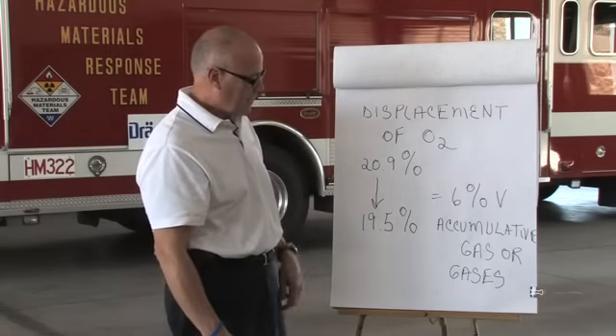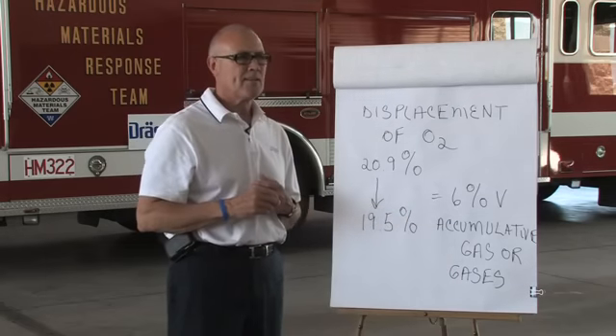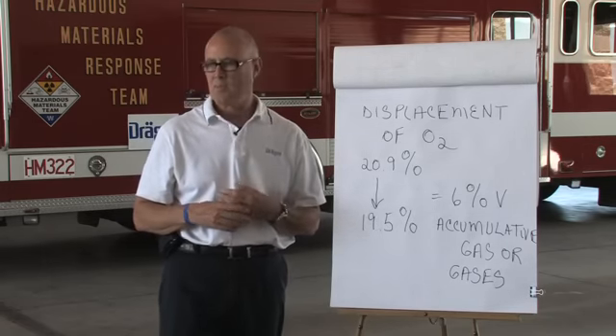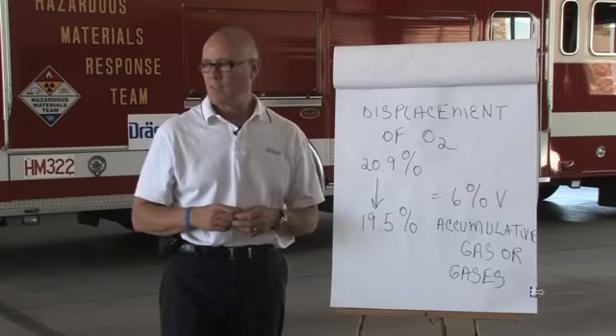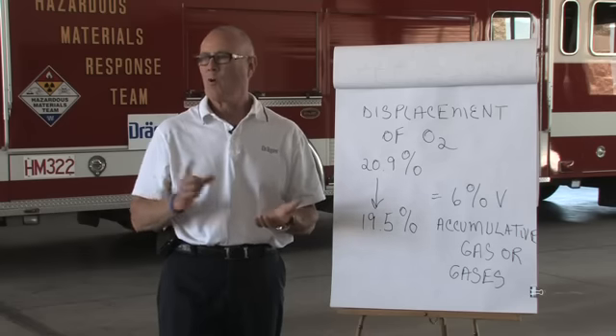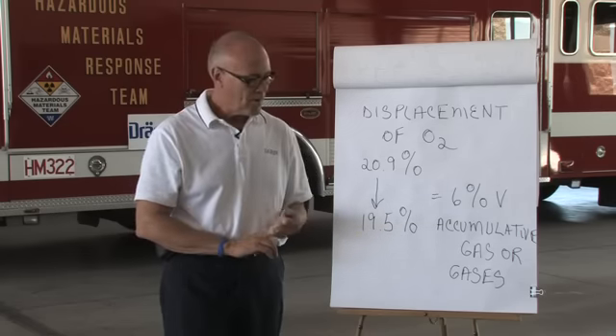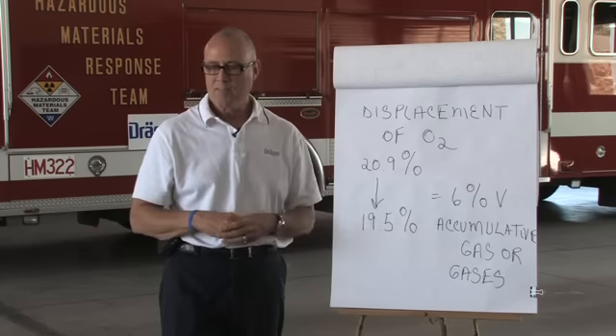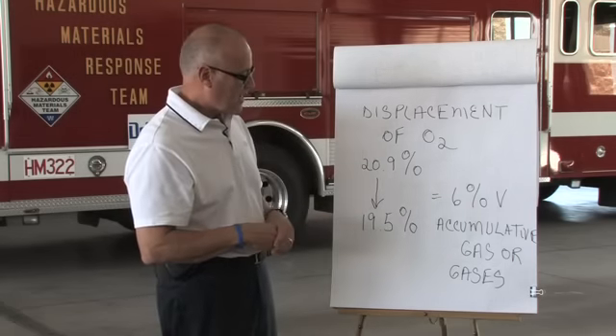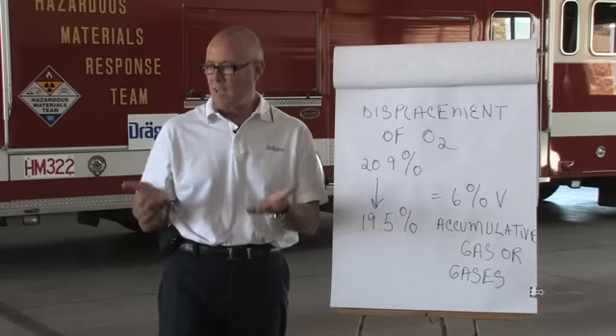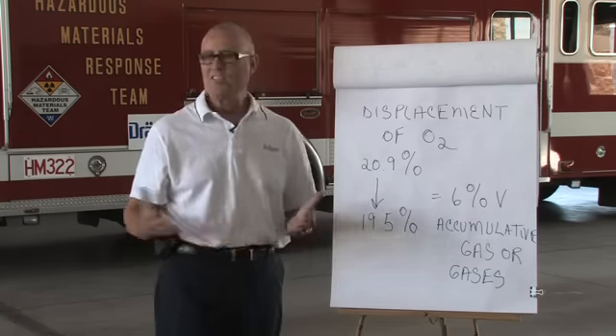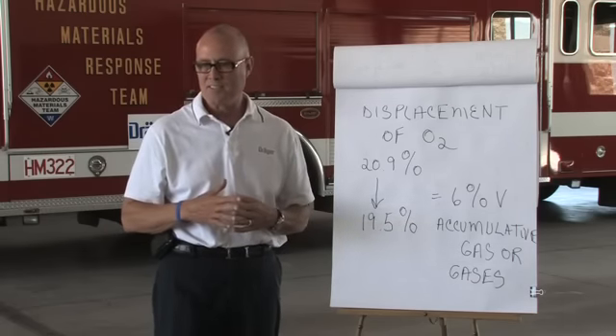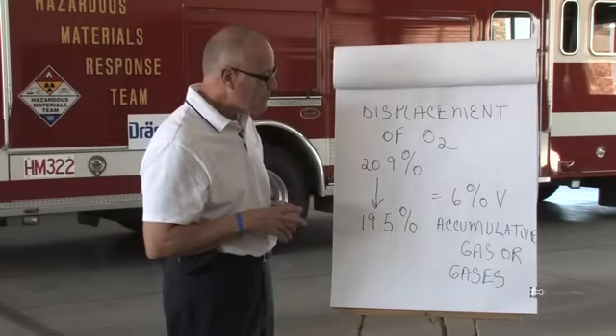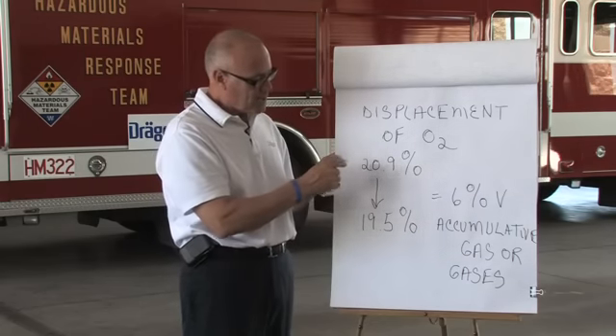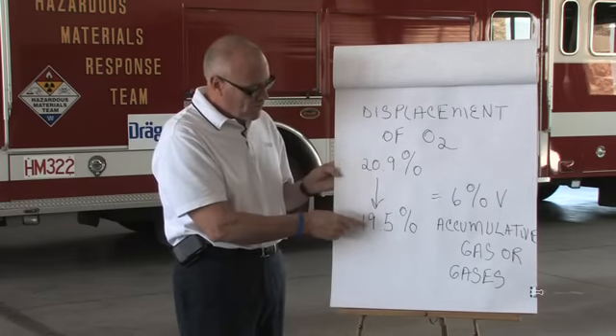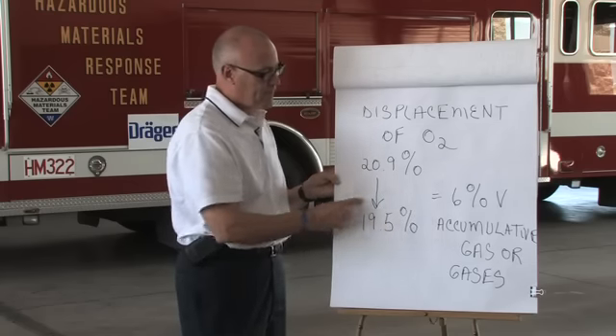And in a manhole, and I say manholes because when I grew up in this business, I grew up in the safety business. And for 20 years, I sold instruments to municipalities, water districts, sanitation districts, where that's what they do. They enter confined spaces, especially manholes. And if it's not carbon dioxide that's creating the oxygen deficiency, then it's a lot of H2S and a lot of methane gas that's creating the oxygen deficiency. So the whole idea of the Draeger meter is to make sure that when you get down to this 19.5 marker, you're getting an alarm.